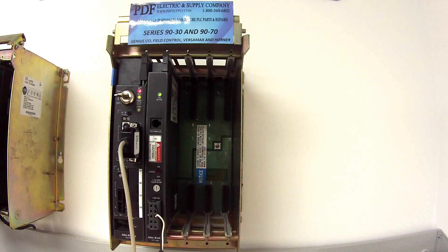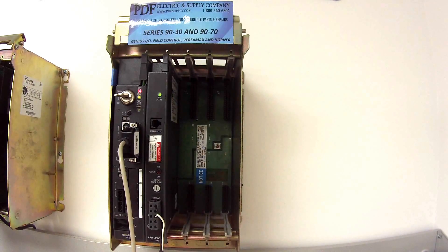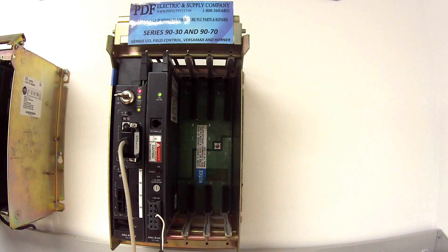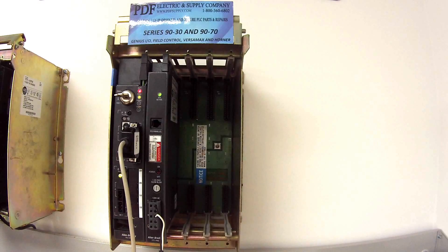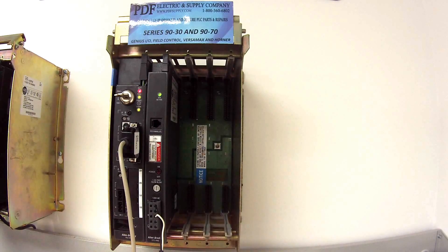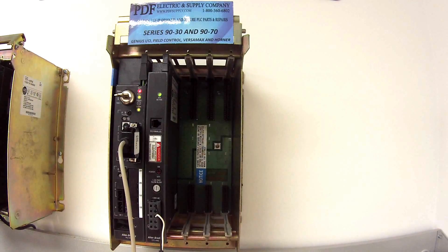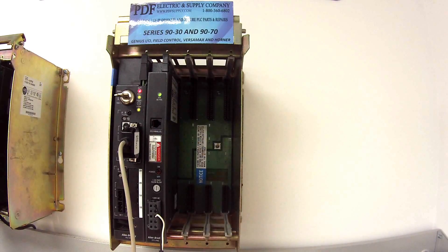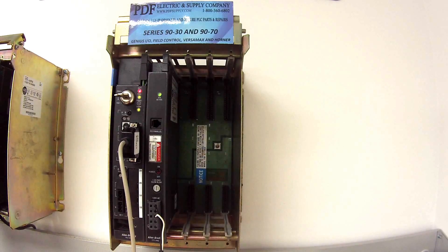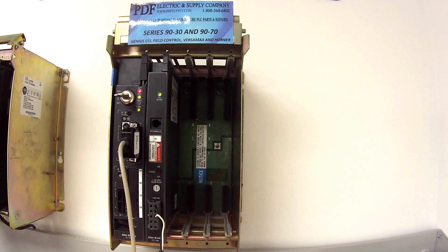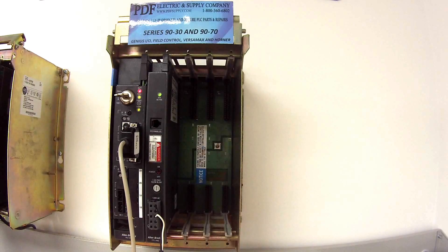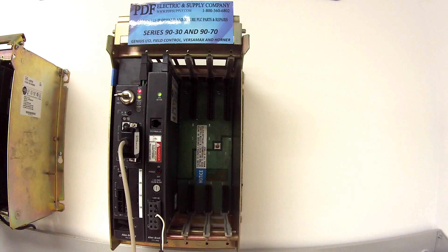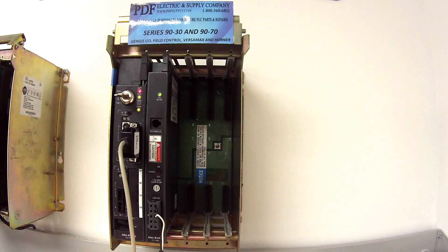That's just a couple things that we would do. Now if it remains in run mode, we typically think that it's a good working processor. If it fails, then we'll look a little bit deeper into it. We'll see exactly if we can find out through the processor status what the error was, why it failed. We may take a deeper look at it.